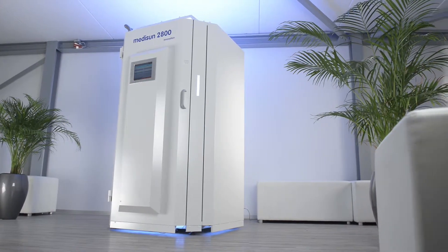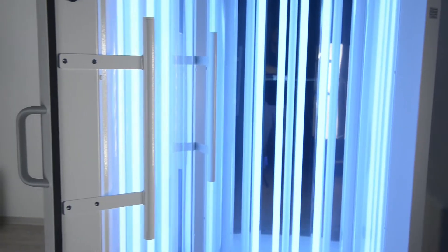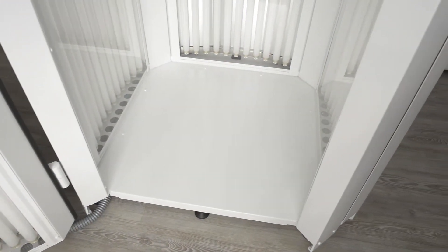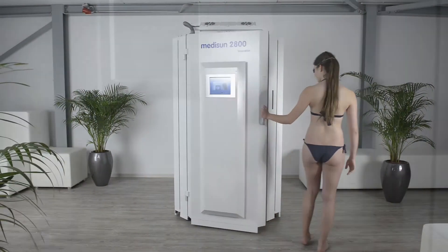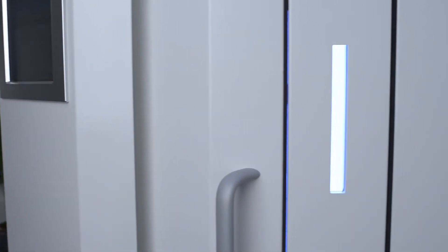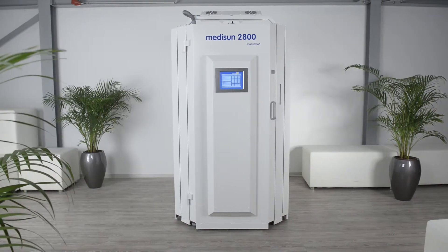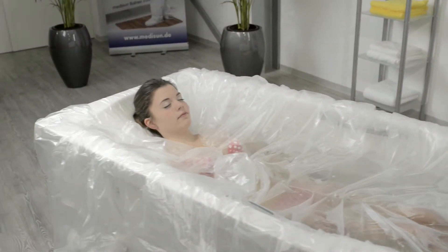More advantages include the built-in fall-over protection for unstable patients, multiple grab handles in the interior, a fixed bottom plate for optimum stability, automatic switch-off of the UV lamps when opening the cabin door, and an optional window for patient monitoring. MediSun 2800 Innovation is also eminently suitable and approved for outpatient phototherapy.